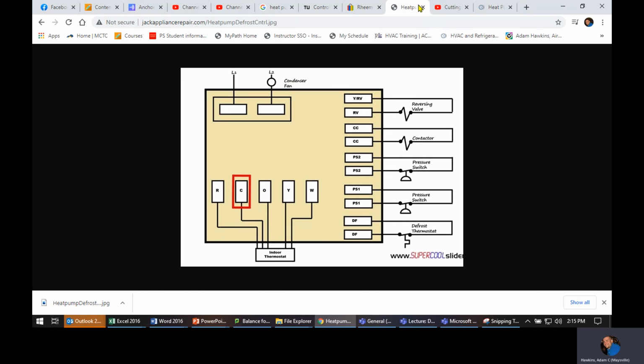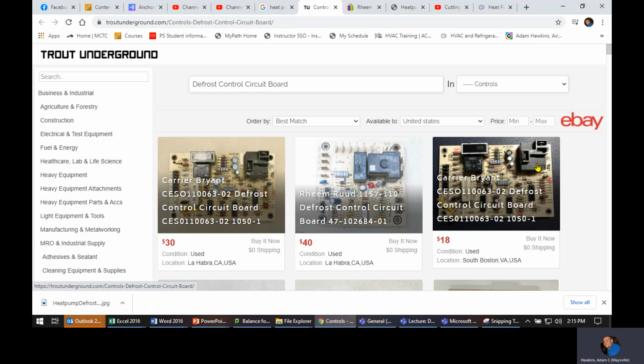So first of all, why do we need a defrost board? We need a defrost because that unit could go below freezing. The coil could get below freezing, stay there for a long time. Obviously, if it's sitting outside, it could be colder than freezing pretty easily, because even if it's above freezing outside, that coil, or that saturation temperature, is going to need to be about 20 or so degrees, 30 below. Most of the time we're more like 20 below, I think, on the heat pumps on the outside. So your indoor minus 30, outdoor plus 20.